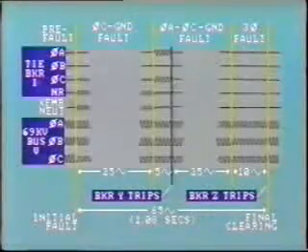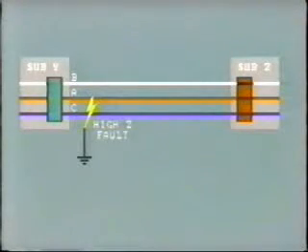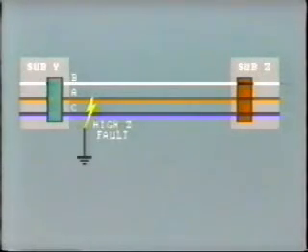At this point, breaker Y finally trips to clear one end of the faulted line. The tripping occurs 30 cycles after the initial line-to-ground fault started. This is reasonable since we are dealing with a high-impedance fault. Thus, the level of fault current is low, resulting in a relatively long operating time.